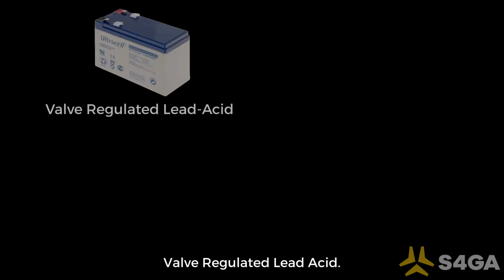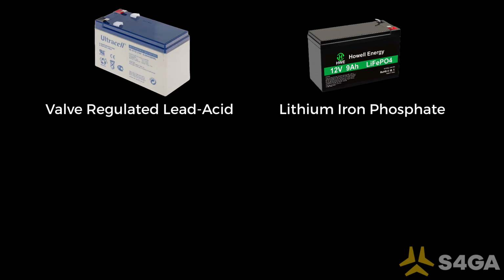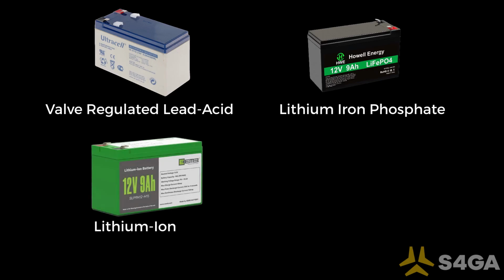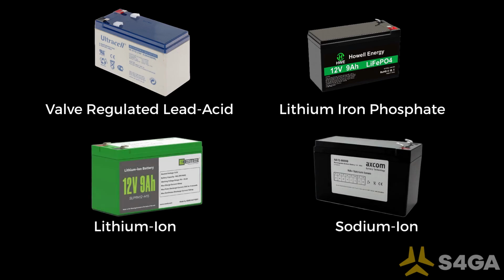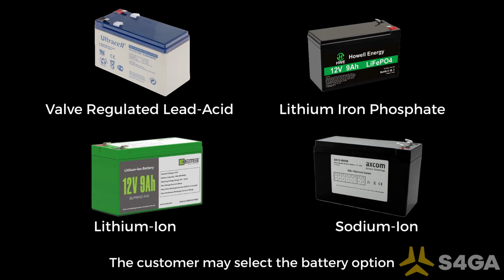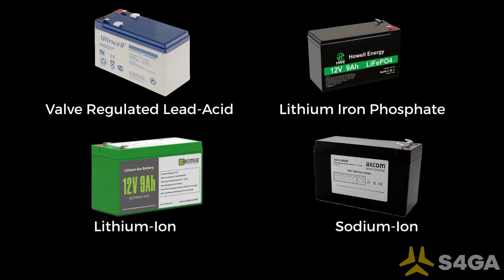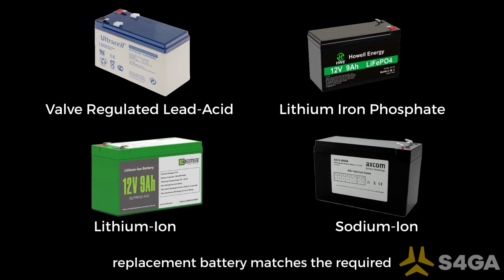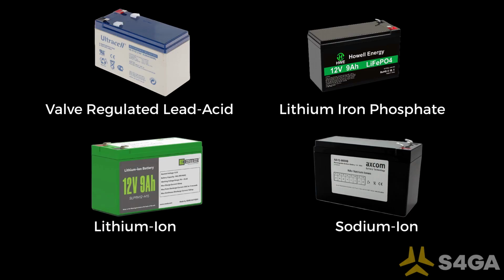The SP-401S is available in different battery variants: valve-regulated lead acid, lithium iron phosphate, lithium-ion, sodium-ion. The customer may select the battery option best suited to their operational needs and environment. Before installation, verify that the replacement battery matches the required variant and voltage rating.